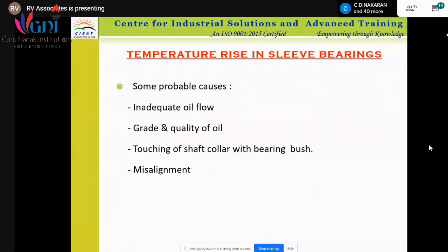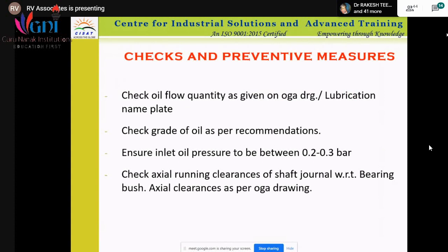Then there is a temperature rise in bearings, because of inadequate oil flow. Maybe low quality oil is used for cooling. Maybe the shaft collar is touching the bearing bush. Misalignment. Because it is an electromechanical machine, all these failures are possible. What we do is always check. How do you check? As told during the visit, you just keep your hand on the motor, and you will feel the temperature and vibration. Similarly, all data has to be checked in parallel.